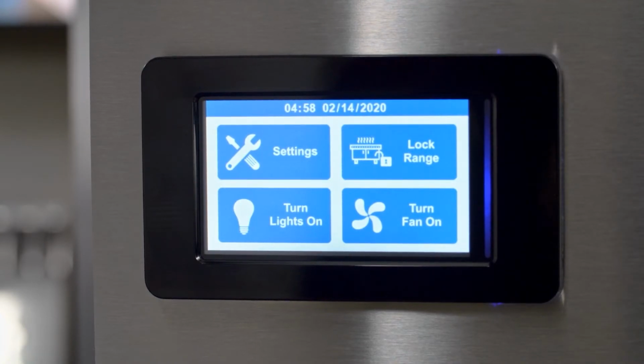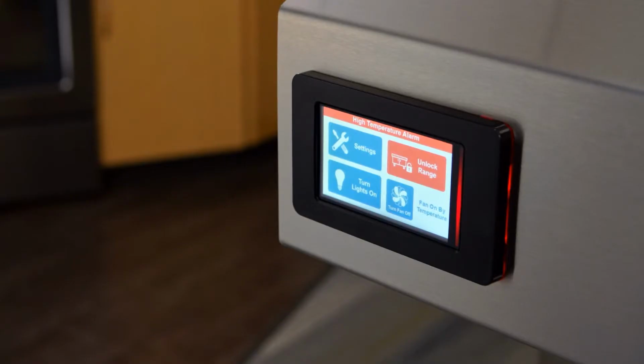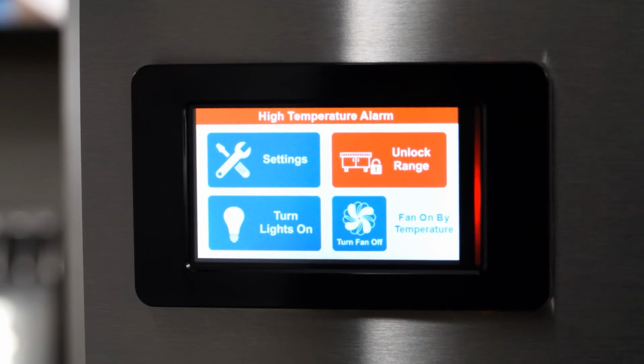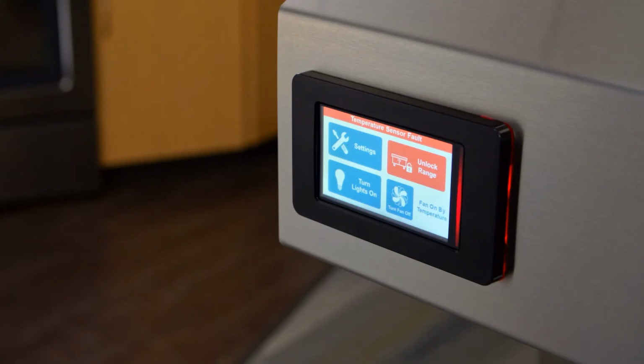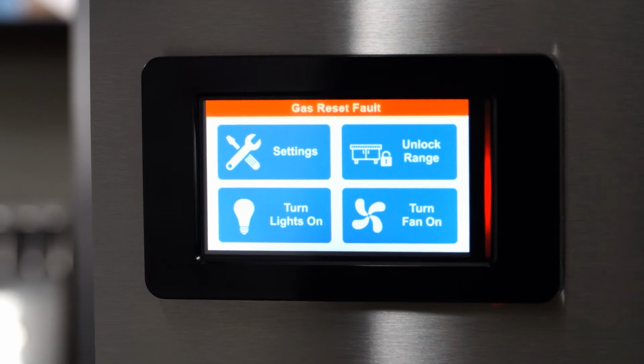The Fire-Ready Range Hood also has the ability to detect and display faults, showing them in the top notification bar on the touchscreen, replacing the standard time and date information. If there is more than one fault, they will sequentially cycle on the notification bar. Any system fault will shut off the range. A high temperature fault will occur if the temperature under the hood has exceeded the high temperature alarm set point, defaulted at 180 degrees Fahrenheit. In addition to the notification, the unlock range icon will turn red. A temperature sensor fault will display when a temperature sensor is not connected properly or is faulty.